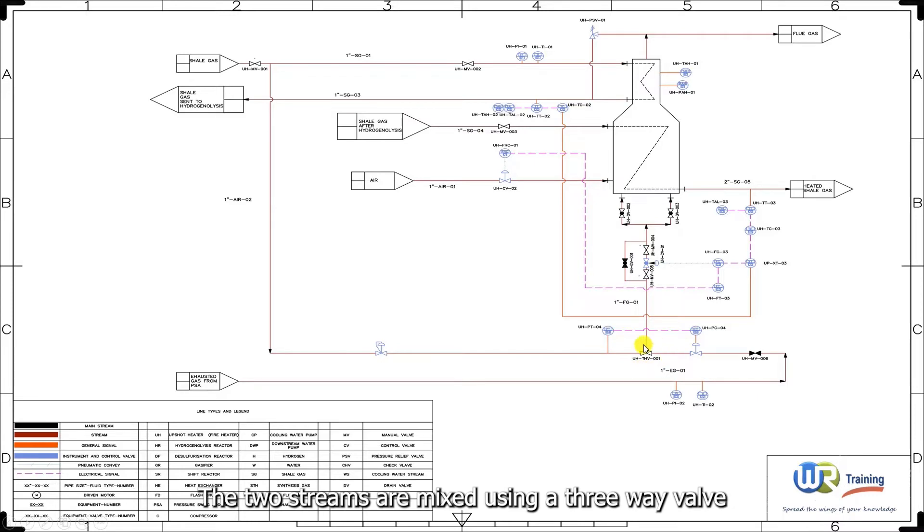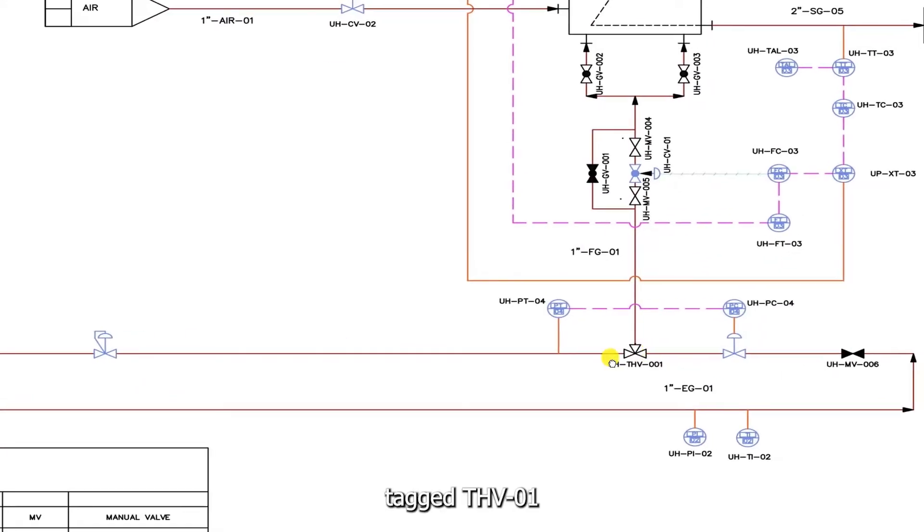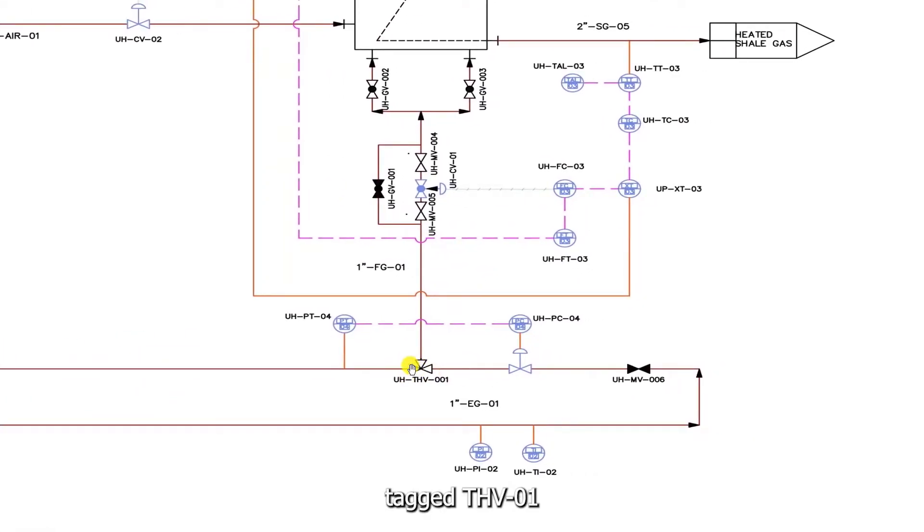The two streams are mixed using a three-way valve, tagged THV01. The control of the gas mixture is done through this control loop. We'll come back to it in a few moments. Now, the gas mixture flows through a one-inch pipe, three valves in a series, two manual gate valves, and one control valve, tagged CV01.